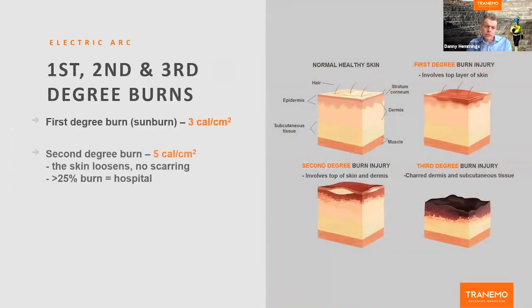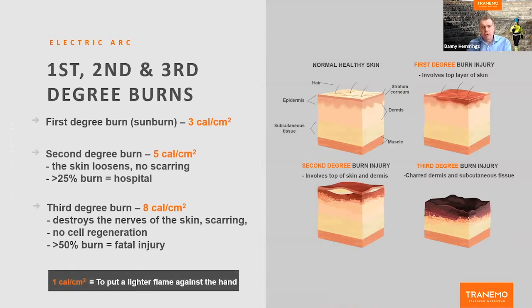So when we look at the impact of thermal injuries, we're referring to first, second, and third degree burns, and to put that in some kind of context, you see there on the pictograms the cutaway of the skin layers. As I'm sure you're aware, the skin is made up of multiple different layers and is geared to protect itself to a certain degree. So for instance, if you apply a calorific rating to first, second, and third degree burns, when we talk about calorific rating, this is incident energy, and incident energy is measured in calories per centimetre squared. If you look at a first degree burn, the most common one we've all probably had at some point would be sunburn. If you apply a rough incident energy to that, you're looking at approximately 3 calories per centimetre squared.